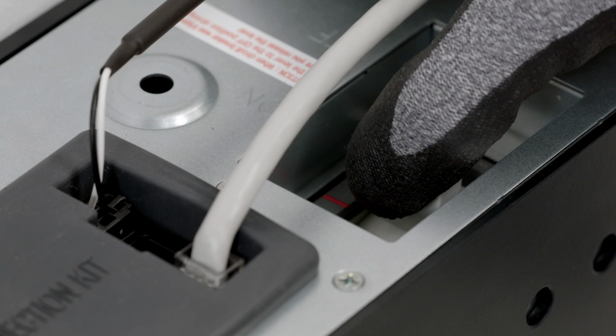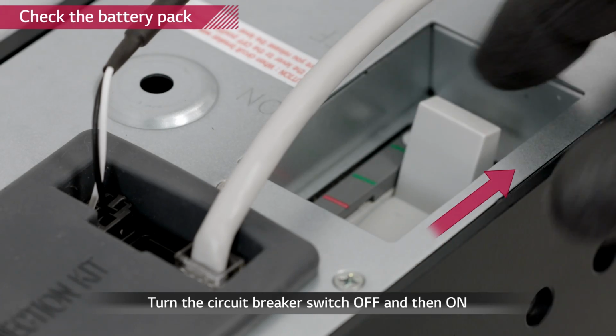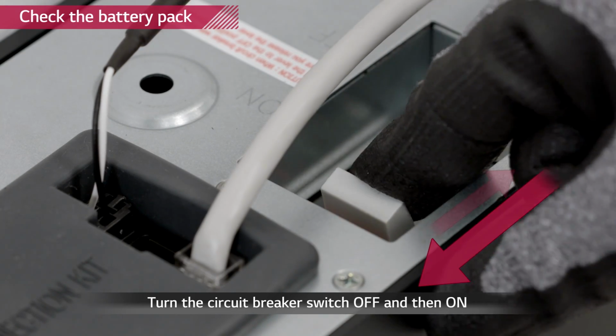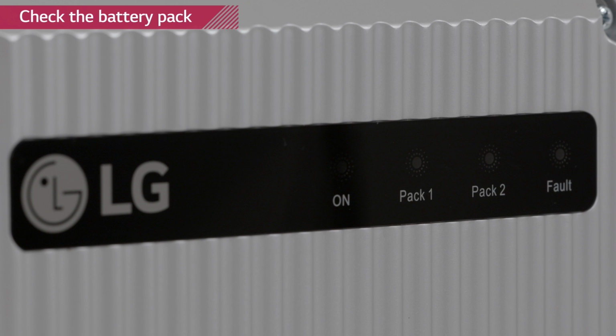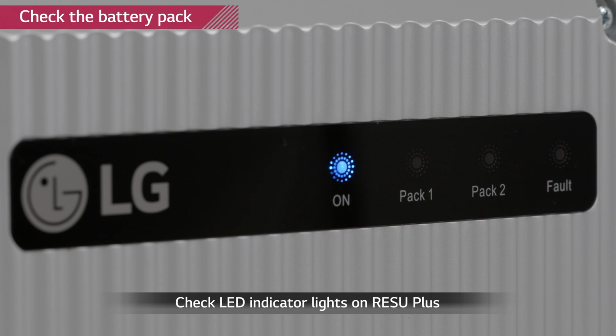Turn on both RESU packs by moving the circuit breaker to off position first, then to on position. The 3 lights at the indicator of the RESU Plus will appear if the installation is performed properly.